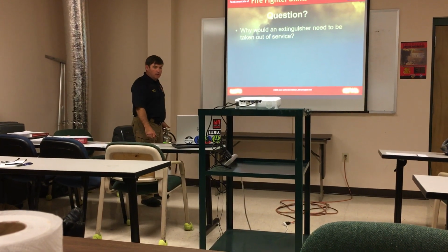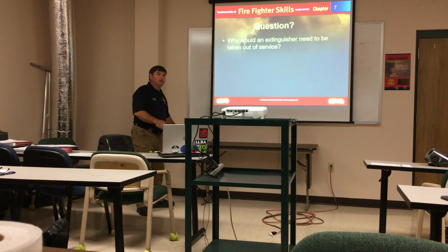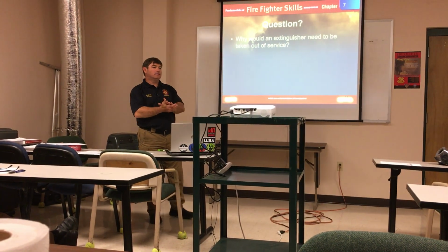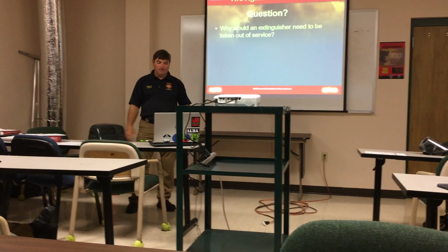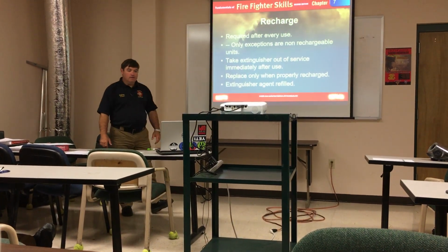Alright guys, why would an extinguisher need to be taken out of service? Leaking. Leaking? What else, Tyler? Not pressurized. How do you know how much pressure's in it? Well, you go by the gauge. Okay. What else? Not having enough weight to it. Not enough weight. That's right. Very good.